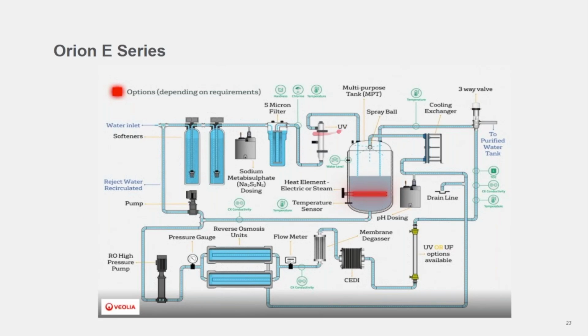Moving on to the E series here, this also shows a number of options which are available for the Orion units, and those are things like sodium metabisulfite dosing between the softening and the 5-micron filter for free chlorine removal. After the 5-micron filter is an option for a UV, should you wish to manage microbial growth at the front end there for the multi-purpose tank.